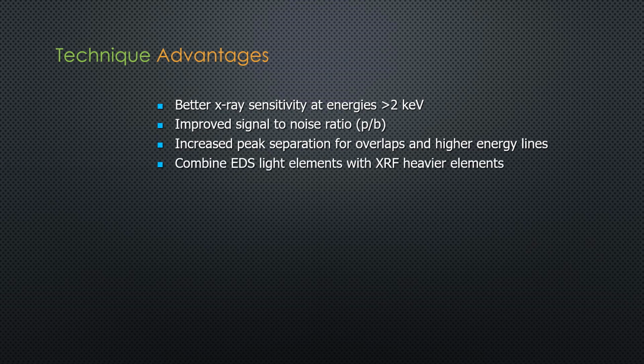Combine your light element EDS analysis with the heavier elements from your Micro XRF units, all in one single application. By combining these two technologies, we can perform EDS and XRF at the same exact sample location without ever moving your sample. XRF is 100% non-destructive and has no charging effect on your samples.